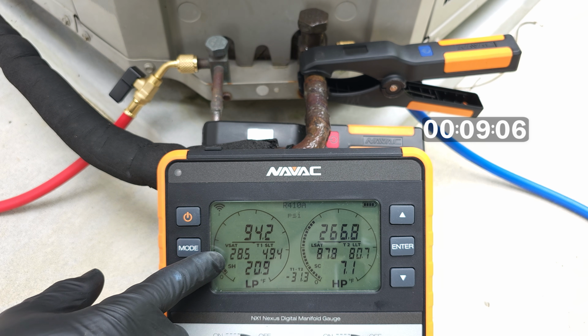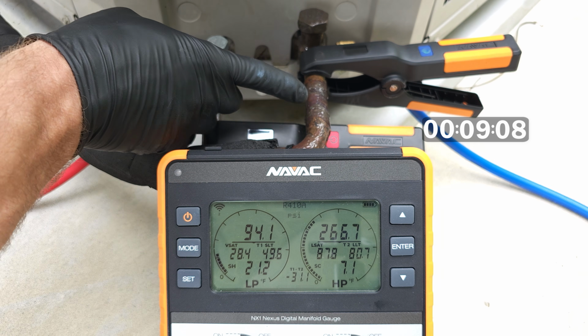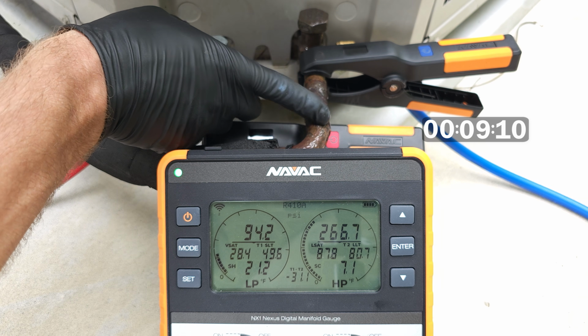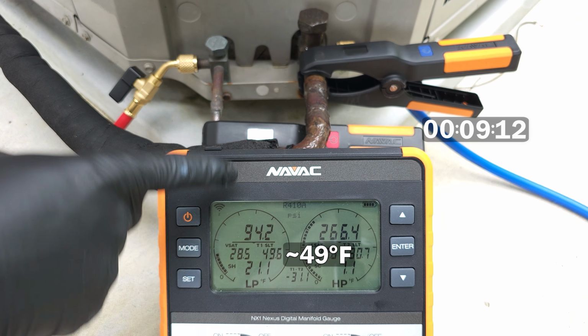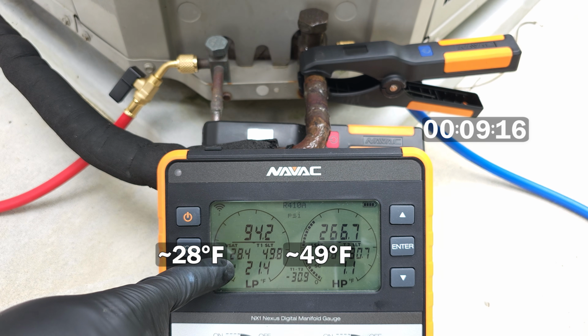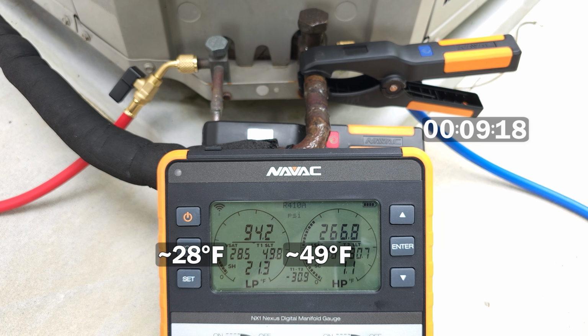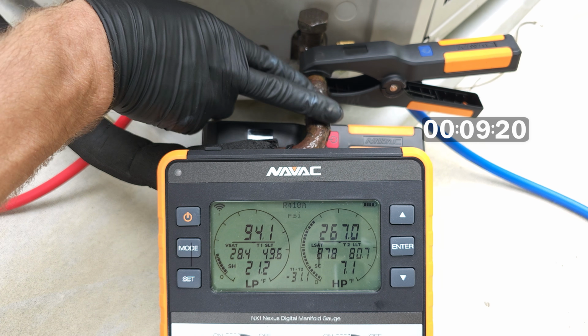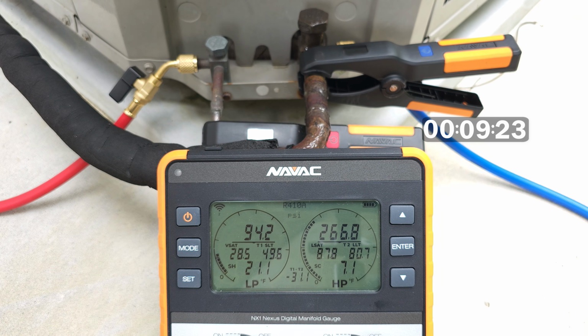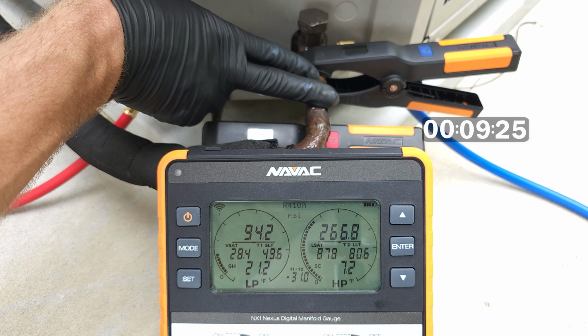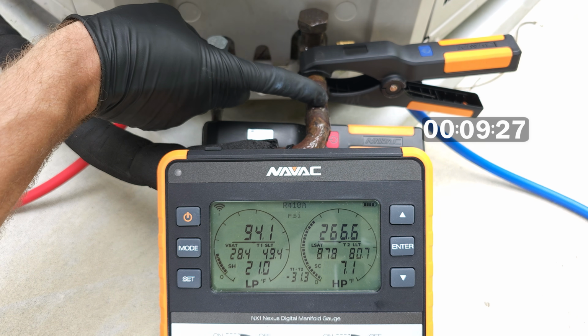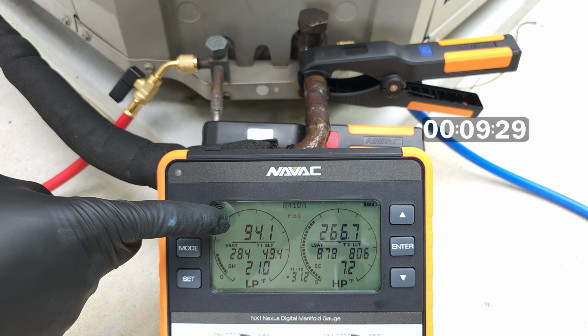And so eventually what's going to happen is if we keep letting this thing run, this line is going to freeze. Right now you see it's right at about 49 degrees on this line, but the saturated temperature is 28 degrees. It's continuing to lower. And so that's why this is freezing. So we don't want to just dump refrigerant into this system to try to increase the pressure over here, because that's not going to work.